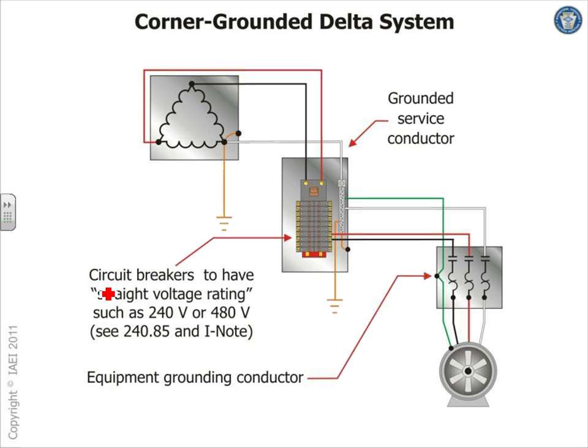Talk about goofy stuff. Isn't that a recipe for disaster when you send an apprentice there? You're looking at a single phase panel fed from a 3-phase system to feed a 3-phase load or single phase load. Imagine sending somebody in there and they see a white wire coming in. What do you think this would be? Neutral.